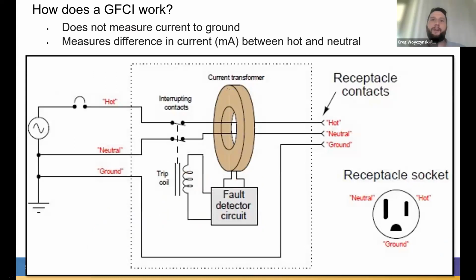How does a GFCI work? So despite its name and that the first letter is G for ground, the GFCI has nothing to do with the ground conductor. The GFCI does not measure current to ground. When we look at inside a GFCI, it's this dotted line here. This is everything that's inside the GFCI breaker or inside the GFCI receptacle. And we can see the ground, that's normally the one with green insulation, that's the bottom pin on your standard plug, is just a pass-through. The ground is passing through the GFCI. No measurements are taken on it. Nothing is done with the grounding conductor.